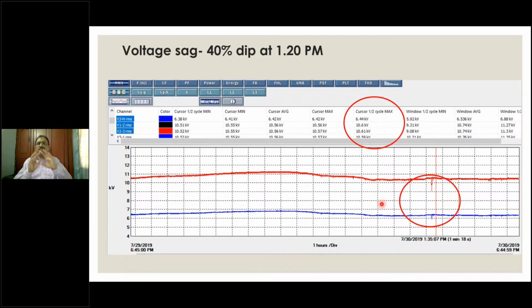Generally, sensitive electronics, including VFDs, can read this very quickly and fold. They will disconnect the supply, looking at it as a danger to the equipment. To protect the equipment, they will fold, and that is when you will find that the equipment has stopped. You will wonder why it has stopped. You will go and check everything again. If nothing is wrong, you will switch on, and it will start running, because by then the voltage is restored. So this is what we have to understand.